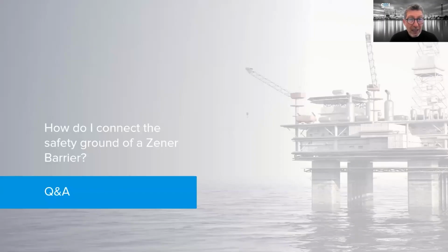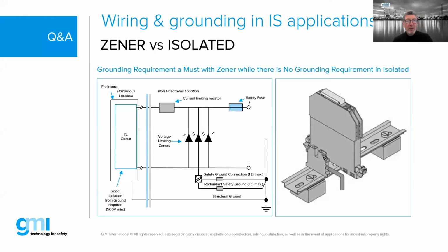How do I connect the safety ground of a Zener barrier? Well, here we go, Bob. This is all yours. Well, this kind of shows what we talked about. Notice that the Zener barriers will still be mounted on a DIN rail, but the important thing to note is that you can tell the difference just by looking at a barrier, whether or not it's a Zener or a galvanic, because typically you're going to see those little earthing tabs on the outside of a Zener barrier. But realize that the earthing of that safety ground is also grounded straight into our DIN rail.